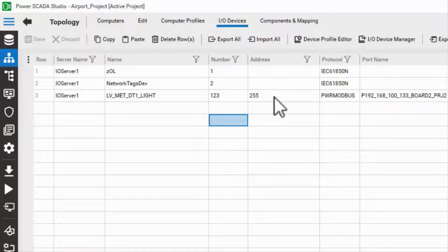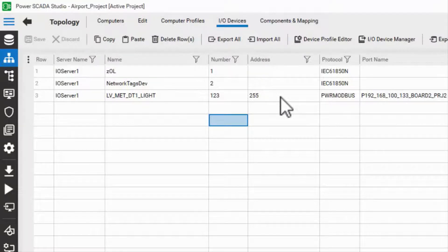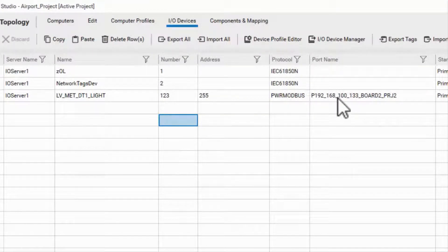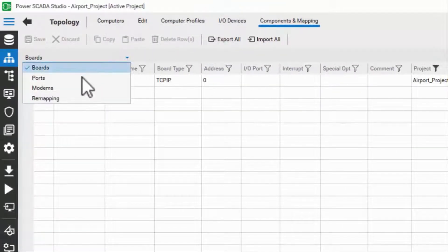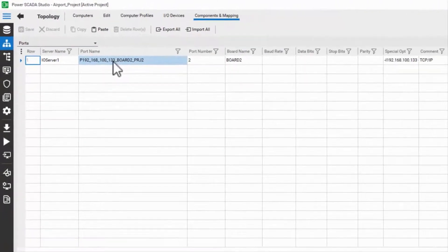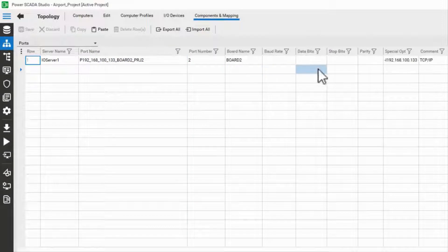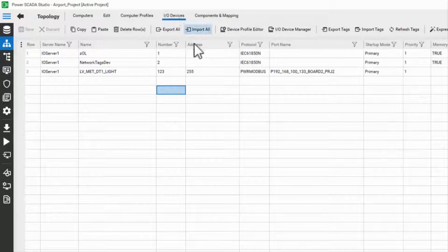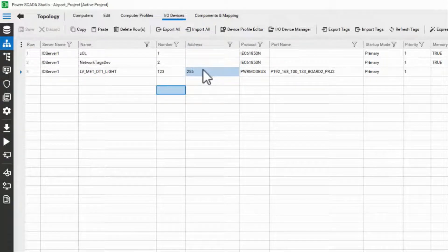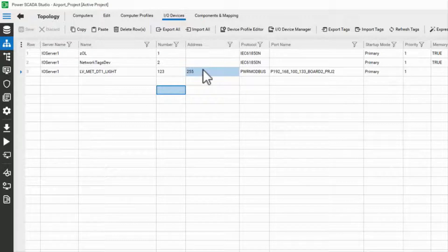Different drivers using different protocols use the various addressing fields and databases differently. Power Modbus sets its Modbus address in this address field, then references a port in the ports database, found under components and mapping. This port contains the IP address in special options. I.O. devices communicating over Ethernet, by contrast, store their IP addresses here in the I.O. devices database, and they all reference a single I.O. port.